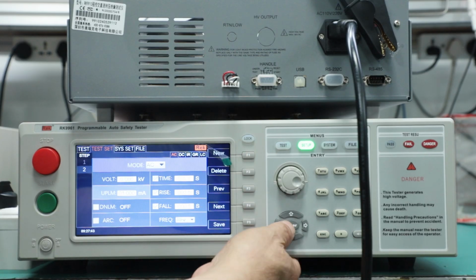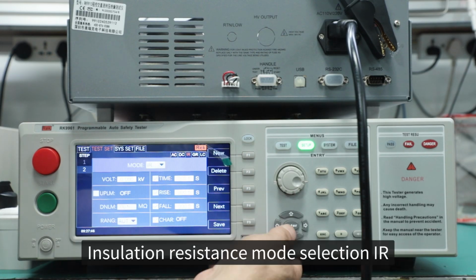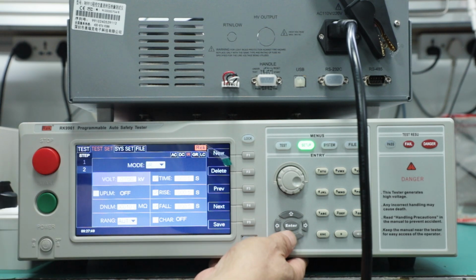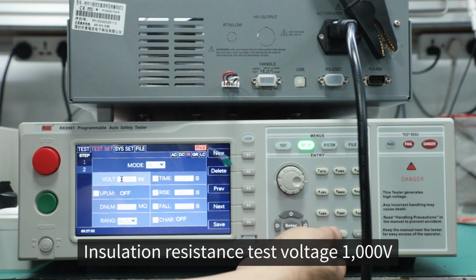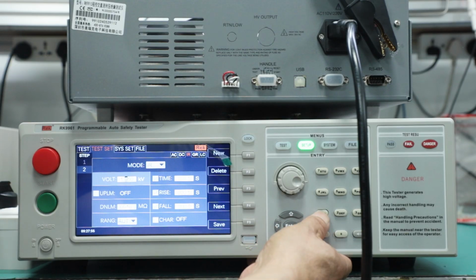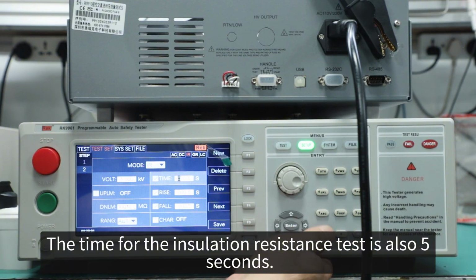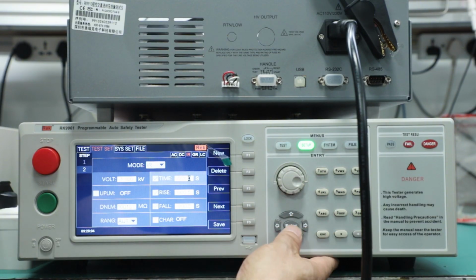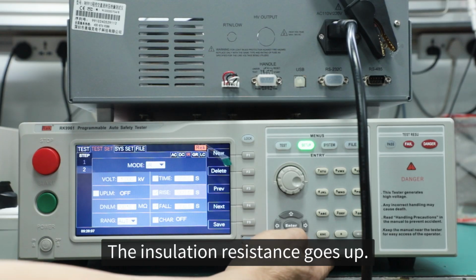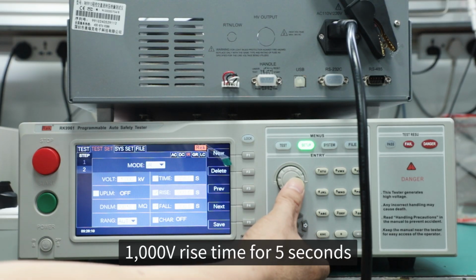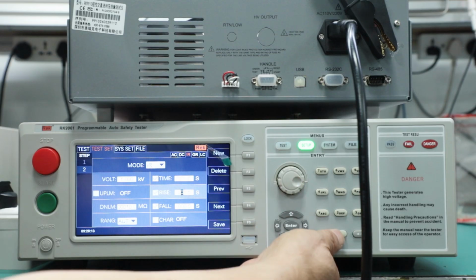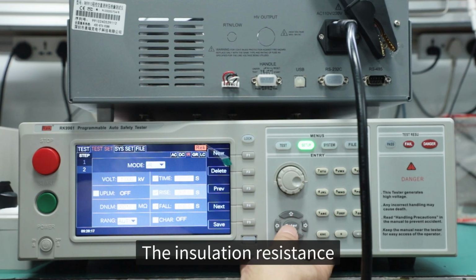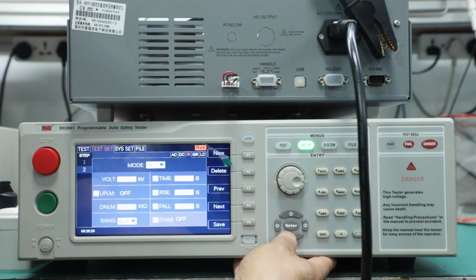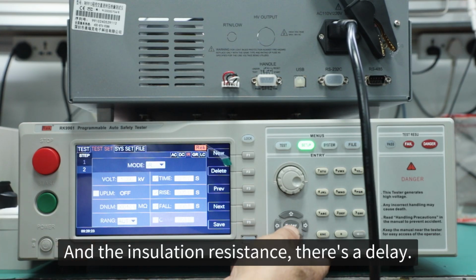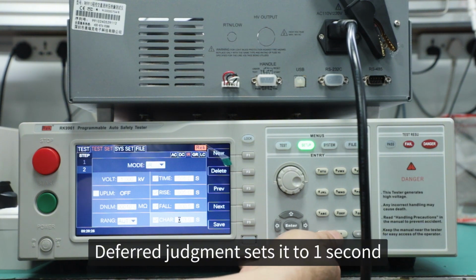The second step is to measure the insulation resistance. Insulation resistance mode selection I. Insulation resistance test voltage 1000 volts. The time for the insulation resistance test is also 5 seconds. The rise time to 1000 volts is 5 seconds, boosted at 200 volts per second. The insulation resistance usually ascends at a constant speed, and there's a delay. Deferred judgment is set to 1 second.